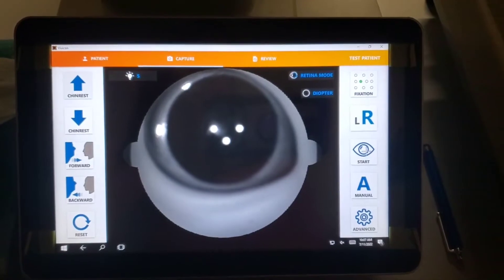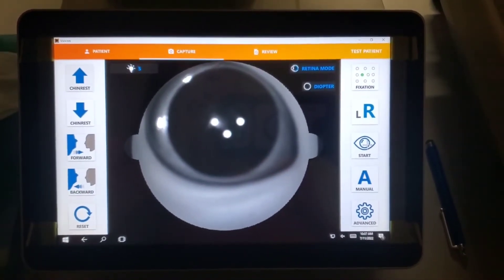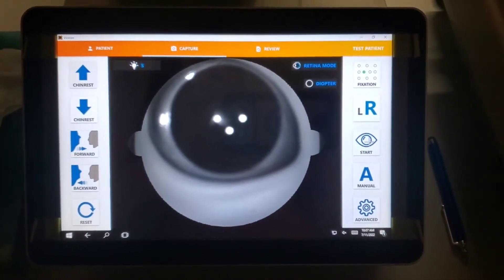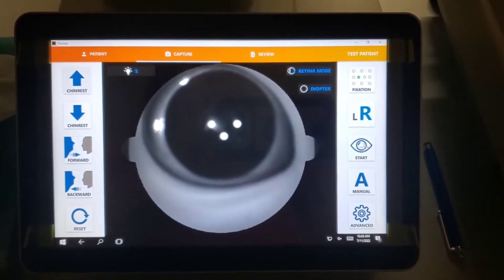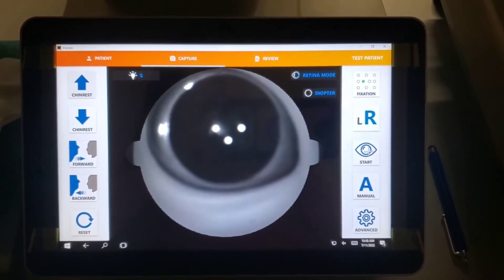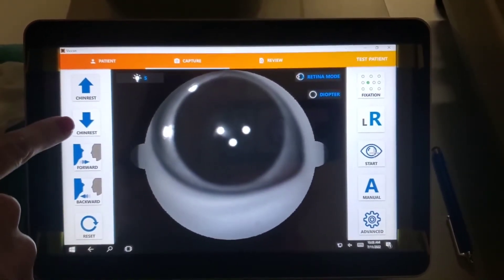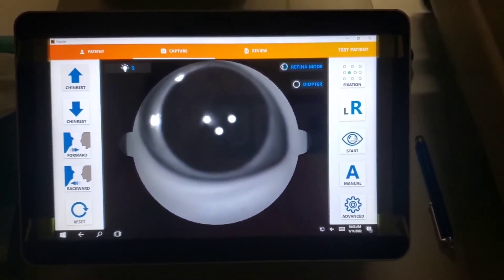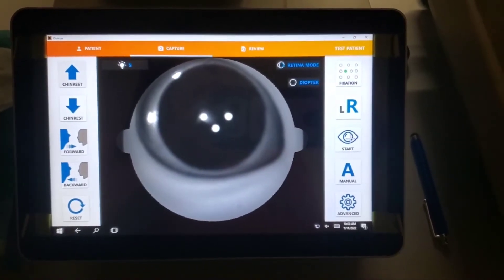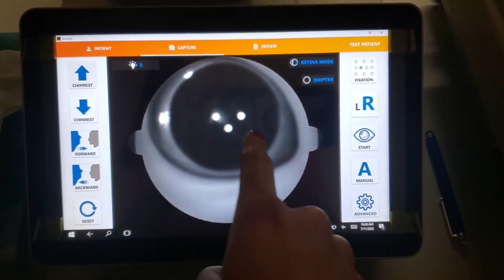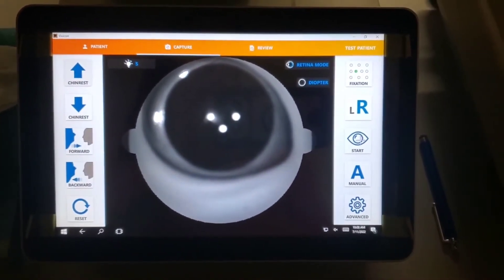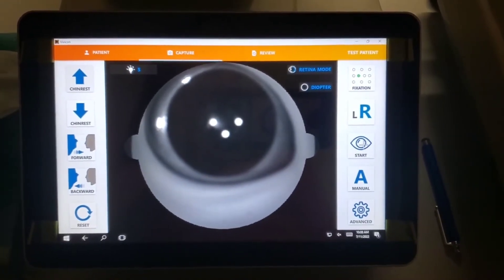Once you have your patient's name pulled up and you've hit capture, you're going to have the patient lean forward, put their chin and forehead into the machine, just like I showed you earlier. Then we need to line up their eyes. We have baby Yoda here again. You can move the chin rest up or down, you can move the whole table up and down, and then sometimes you can even have them move their chair up and down just so that they're comfortable and that you have the eye lined up here. Sometimes it will give you a little red box. It's not popping up right now because we have an artificial eye in here, but it will tell you that it is happy with the pupil alignment for the patient.